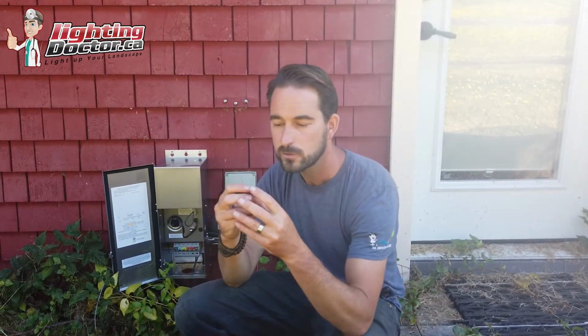The reason we did that in this case is we want to allow for future expansion. The other reason is that anytime you get a slightly larger transformer—this is a 300 watt multi-tap transformer, so it has multiple areas to put the wires in—this used to be a lot more of a concern when you were dealing with halogen systems, because you had to be real precise with the amount of voltage each light was getting to get that to work properly. They had to be between 11 and 12 volts, so you really had to calculate out all your voltage drop and all that kind of stuff.